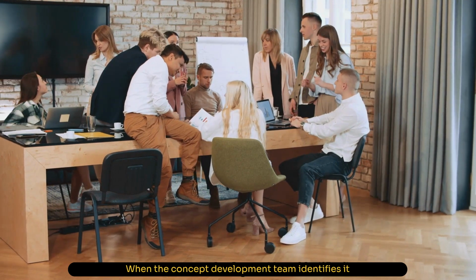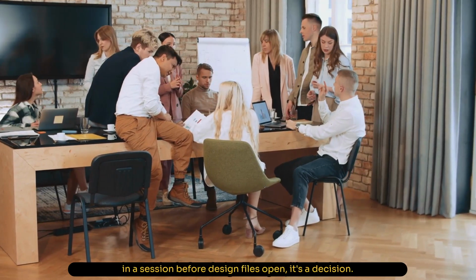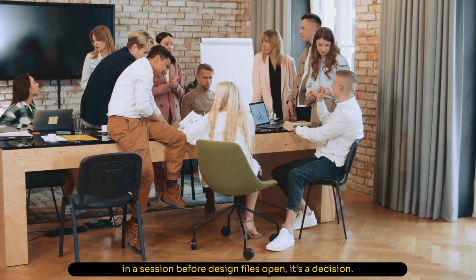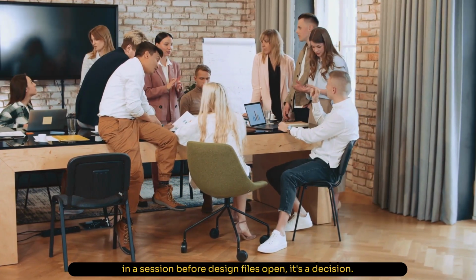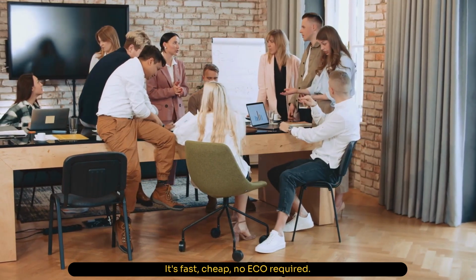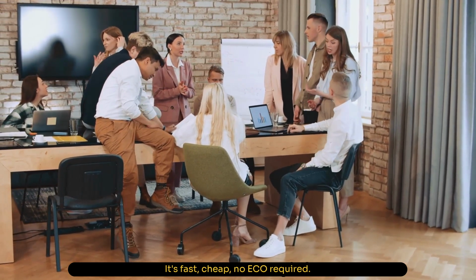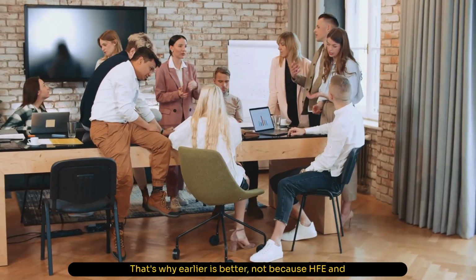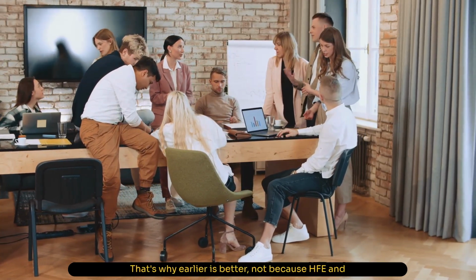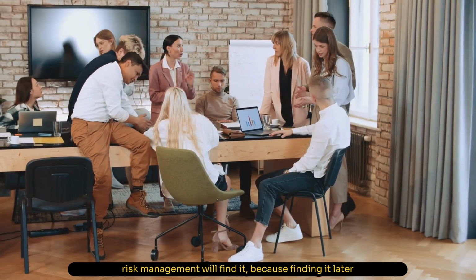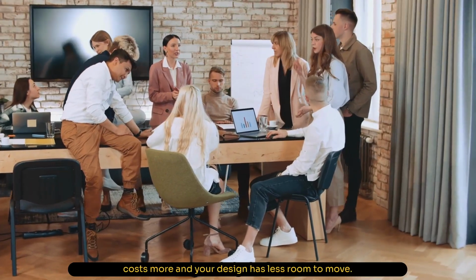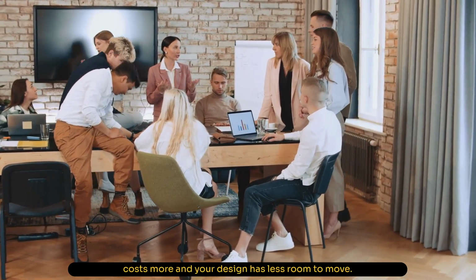When the concept development team identifies it, in a session before a design file is open, it's a decision. It's fast, cheap, no ECO required. That's why earlier is better. Not because HFE and risk management will find it, because finding it later costs more and your design has less room to move.